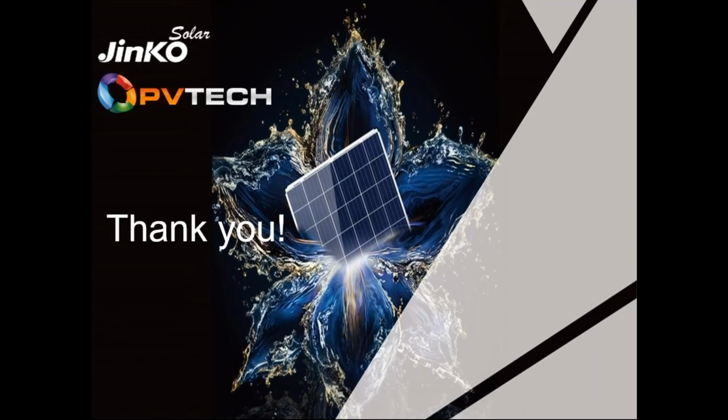So far, yes, we can simulate bifacial, but again, I don't think the PVsyst calculation is quite accurate. It is for all the other technologies, but bifacial is quite new, and you have to consider different factors, not only the albedo, but also the height of the panel, which makes a huge difference. It's an ongoing process, and yes, bifacial will come also in this tool whenever I get some results from the field, because we have different plants running and we are testing the output, and also when the simulation will be really accurate from the software. That's the point. Okay, yeah, understood.